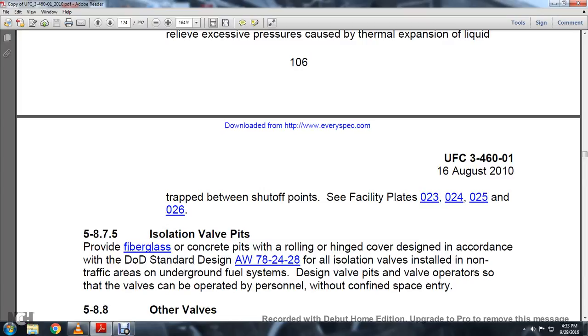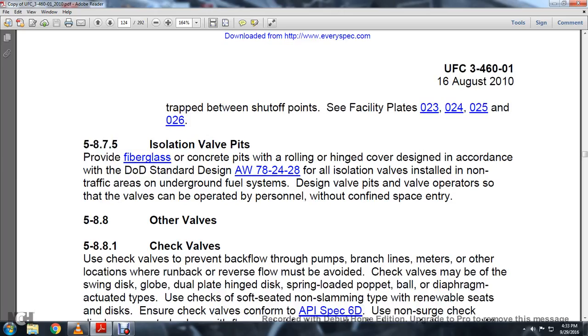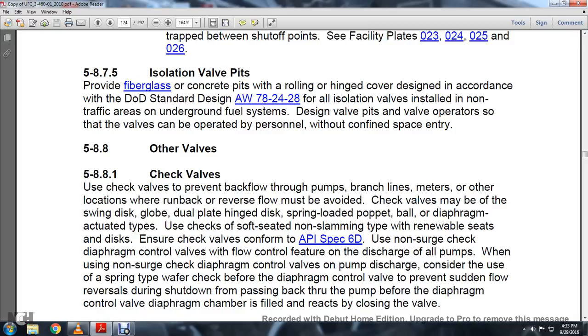5875 isolation valve pits: provide fiberglass or concrete pits with a rolling and hinged cover. Design in accordance with the Department of Defense standard for the isolation valves installed in the non-traffic area underground fuel system. Design valve pits and valve operators so the valves can be operated manually without confined space entry. 588 other valves.